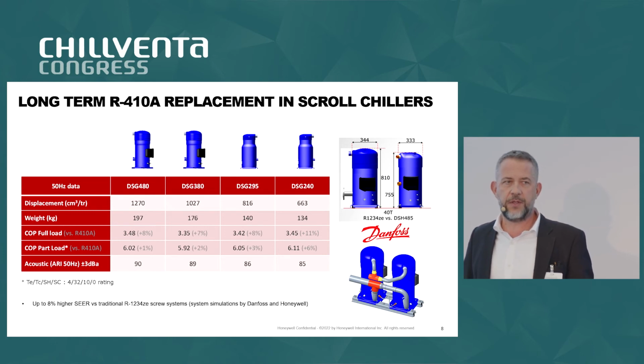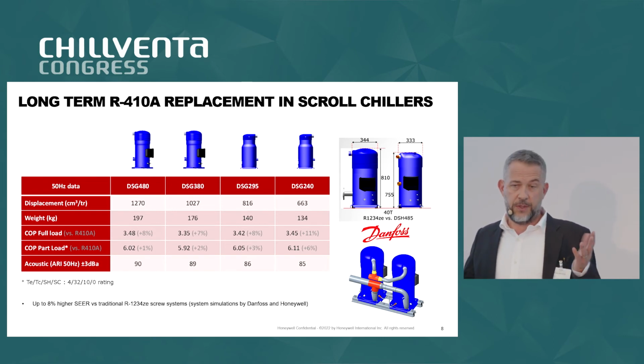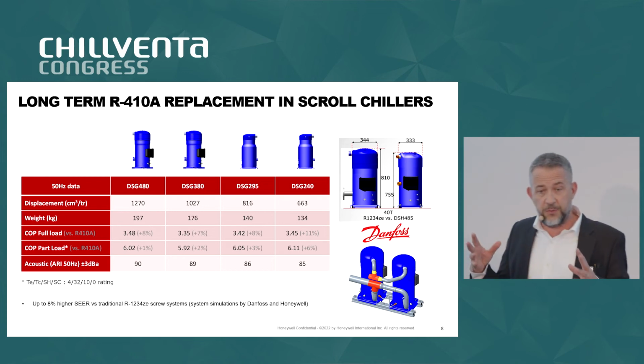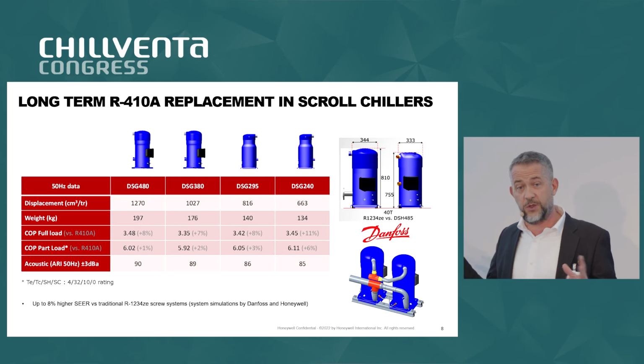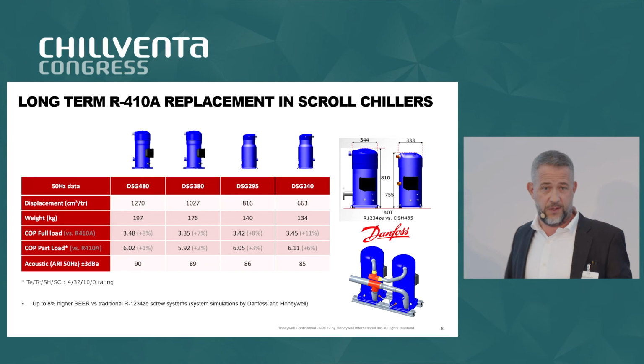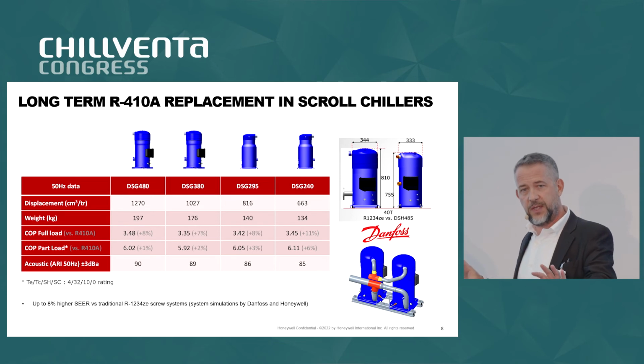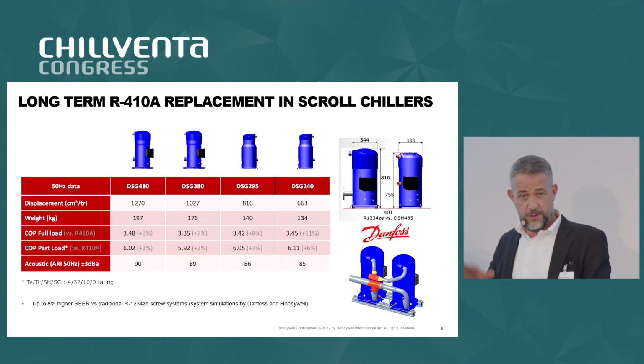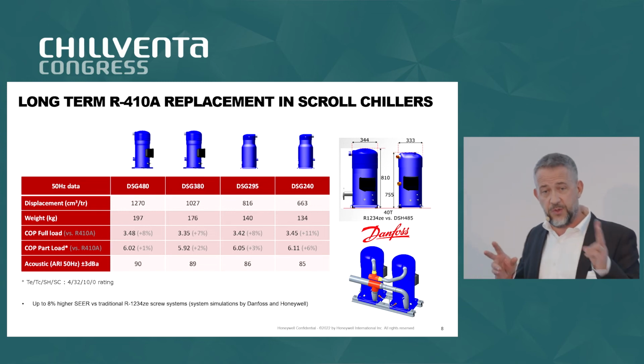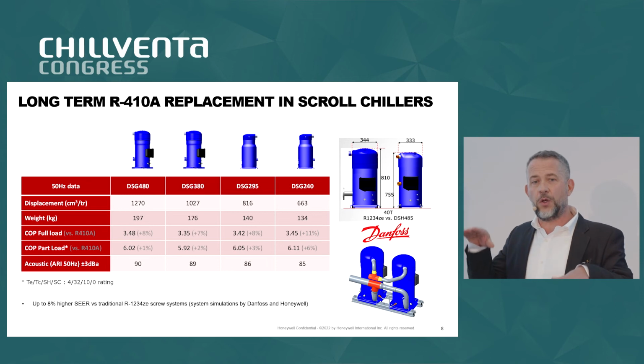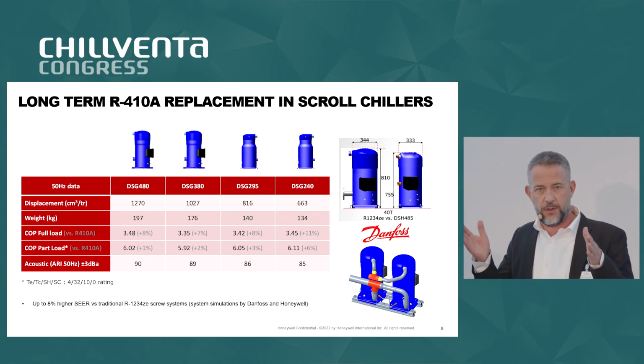Understood, I got your question. So to summarize, the question is variable speed versus fixed speed, okay? Traditionally in this range of chillers, variable speed raises a lot of cost. On this kind of chiller, which can have up to 12 compressors depending on the number of circuits, you have what we call manifolding. These compressors are designed to be matched up to three together on the same circuit, a trio. So you have three levels of capacity already, times two circuits, which makes a lot of steps. This is why in this commercial compressor range, you will have fixed speed for a long time.